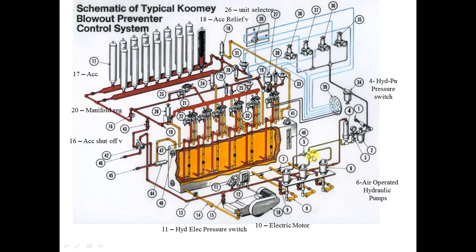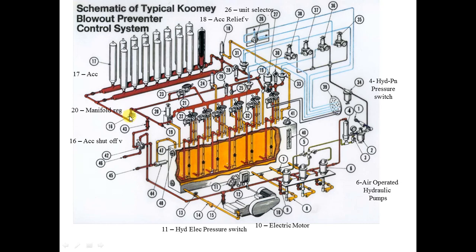Now let's move to the accumulator system. Number sixteen is called the accumulator shutoff valve, also known as the isolation valve. It is always open during operation. If you close it, you can isolate the accumulator from the pumps — for example, to reset the pressure switches and test the pumps independently.